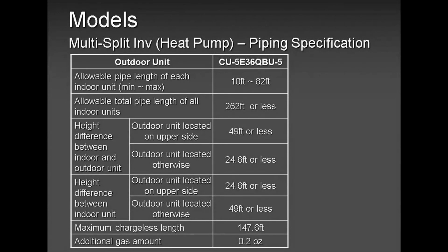You run all the way to the indoor unit, and at the indoor unit is where you're going to use the adapters. For the 24,000 only, it's going to be different. You are going to run half inch suction line from the outdoor to the indoor, and when you get to the indoor, you're going to use an adapter to upsize it to 5/8 and another adapter to downsize it to 3/8.